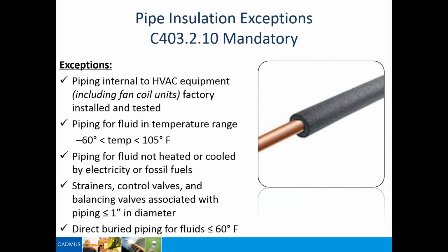So there are some exceptions, obviously. Direct buried piping for fluids less than or equal to 60 degrees Fahrenheit is exempted. Here's our piping range between negative 60 degrees and 105 degrees. Again, those are exempted. And then if your piping is internal to the HVAC system, you don't have to worry about insulating that, primarily because the efficiency effect of an uninsulated pipe is already factored in when they calculate the efficiency for that particular piece of equipment.